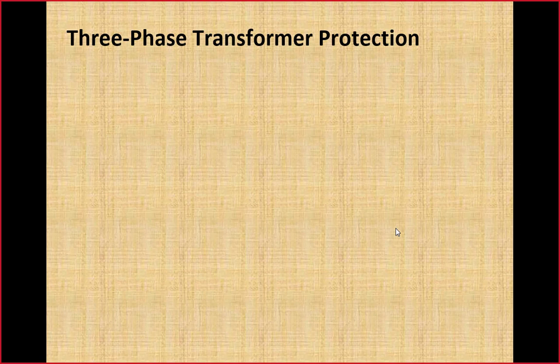Here we start our discussion regarding challenges that we will have to tackle in three-phase power transformers. So power transformation in three-phase system can be done by two means: either by using three single-phase transformers or by using single three-phase transformer. So there is a difference in these two schemes. If the amount of power that we want to transfer from one voltage level to other voltage level is large, and that is normally the case in extra high voltage system, instead of building a very large single three-phase transformer, it is much economical and feasible to build three single-phase transformer.